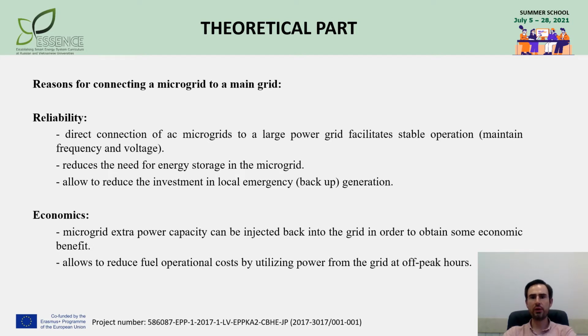So the reasons for microgrid connection to the main grid are also associated with these milestones. As regards reliability, multiple generators of the main grid have a reserve capacity and act as an additional source or slack bus for the microgrid. So direct connection of AC microgrids to a large power grid facilitates stable operation, but only if the power grid is much larger and able to maintain stable voltage and frequency in case of disturbances. When using renewable energy sources, a grid connection may also reduce the need for energy storage in the microgrid. If not all loads in a microgrid are critical, a grid connection may allow reducing the investment in local generation.